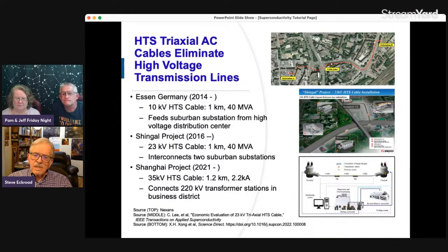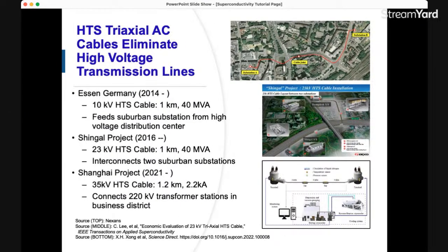The first, and the poster child of commercial applications for AC cables, is the Essen, Germany cable. I've been there and walked that route shown in red in the upper right—it's about a kilometer long, in the very pretty city of Essen, northern Germany. It's a 10 kilovolt, 40 megawatt cable. In the lower right is a high voltage substation, I believe 110 kilovolts, and in the upper right is an urban substation with suburban load. It used to be fed, or was going to be fed, by a 110 kilovolt cable following that route, underground.